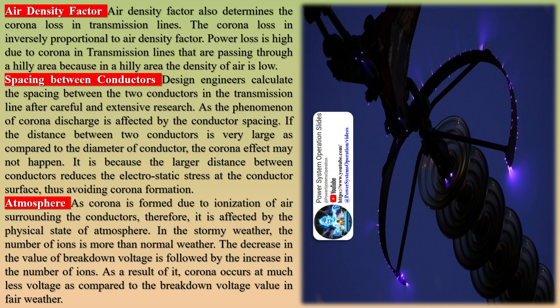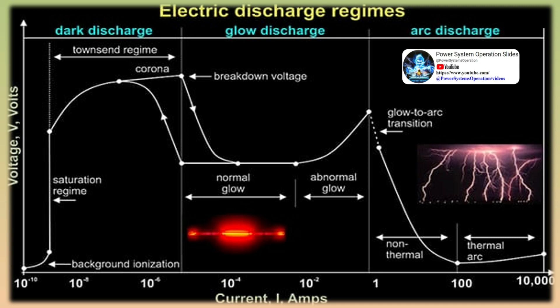Conductor surface: the corona effect depends upon the shape, material, and conditions of the conductors. A rough and irregular surface decreases the value of breakdown voltage due to concentrated electric field at rough spots, giving rise to more corona effect. The roughness of a conductor is usually caused by the deposition of dirt, dust, and scratching. Raindrops, snow, fog, and condensation accumulated on the conductor surface are also sources of surface irregularities that can increase corona. Air density factor also determines the corona loss in transmission lines, and corona loss is inversely proportional to air density factor. Power loss is high due to corona in transmission lines passing through hilly areas because in hilly areas the density of air is low.